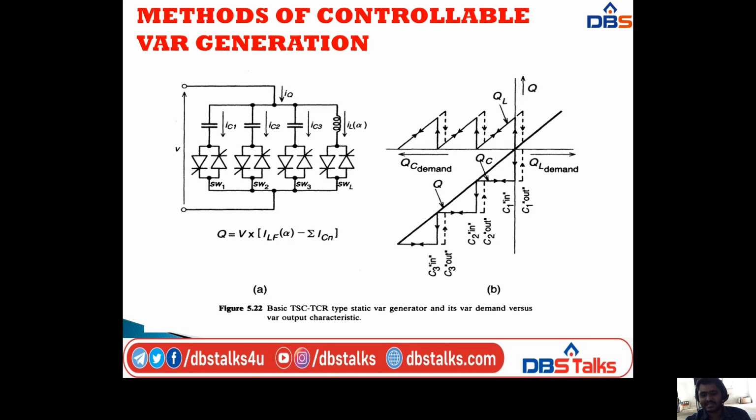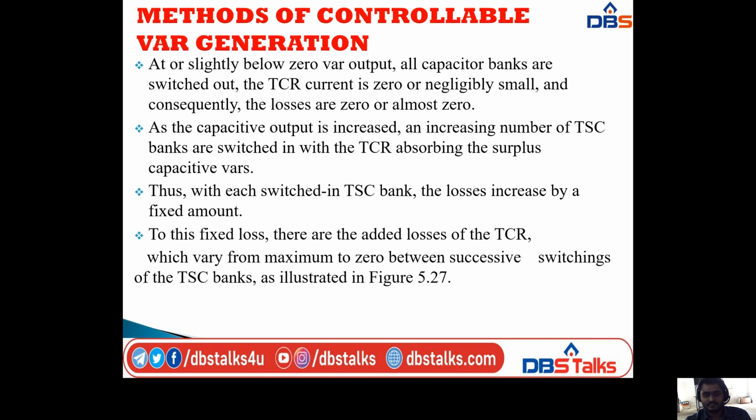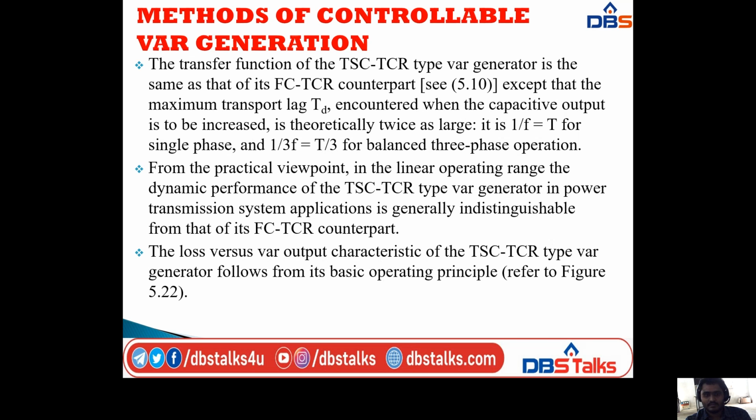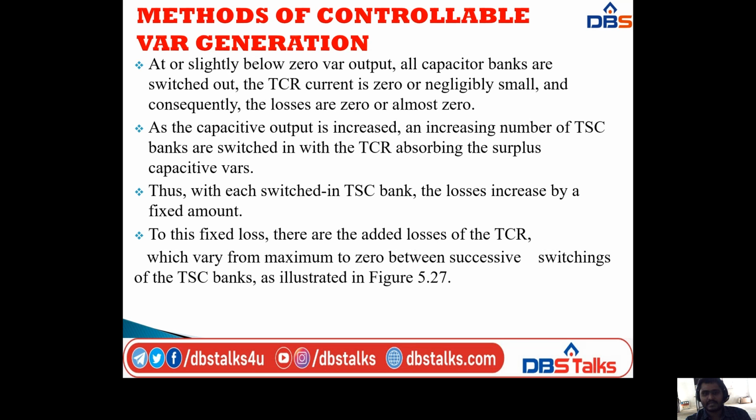So this is the first slide. I'm explaining about these two things. Okay, and next, at zero VAR output or slightly below zero VAR output, all capacitor banks are switched out, the TCR current is zero or negligibly small, and consequently the losses are zero or almost zero.